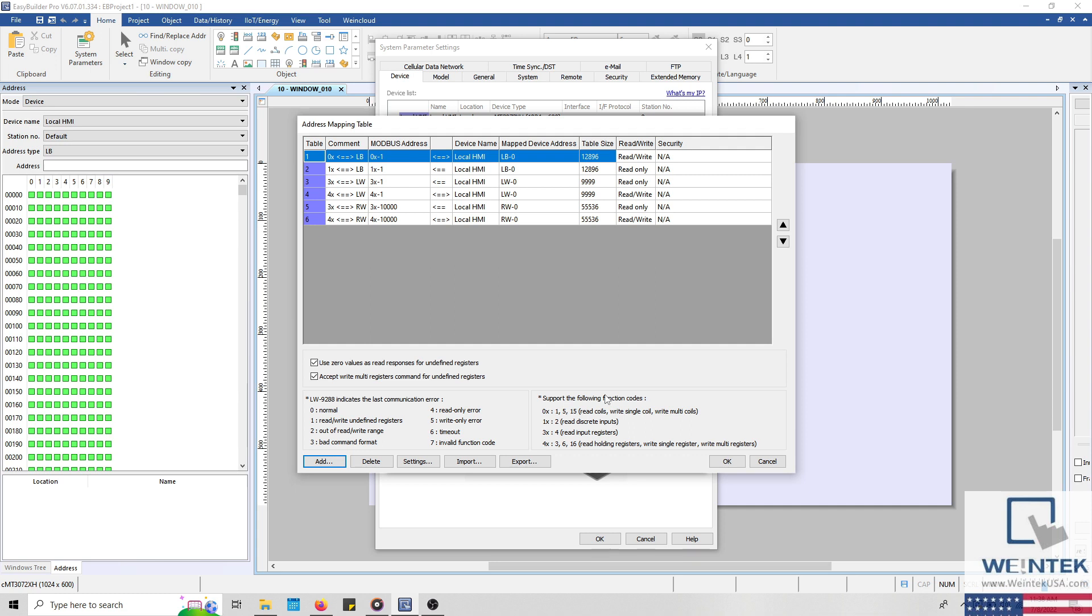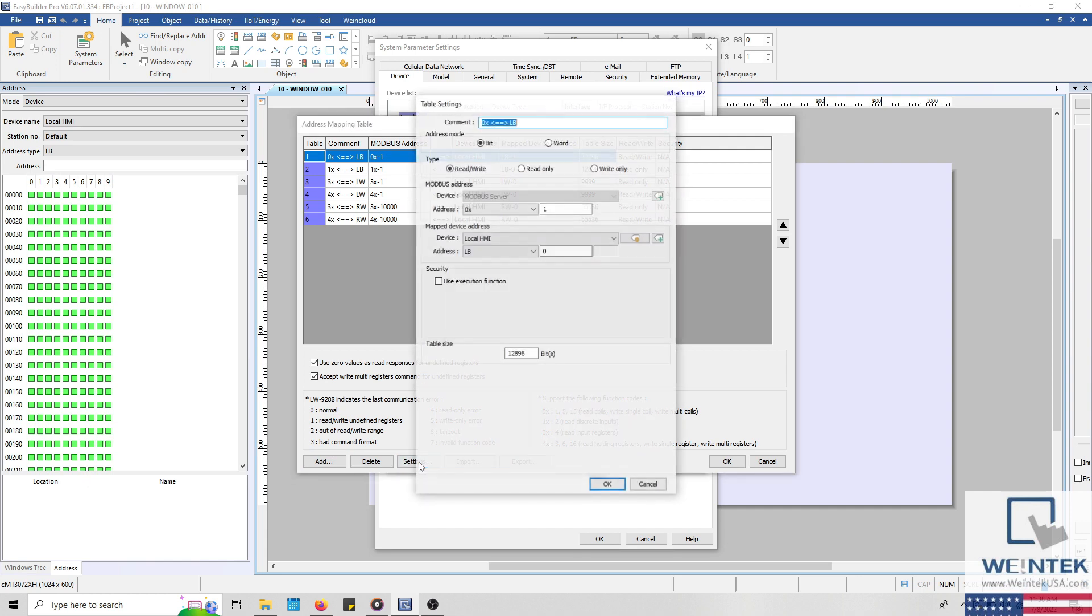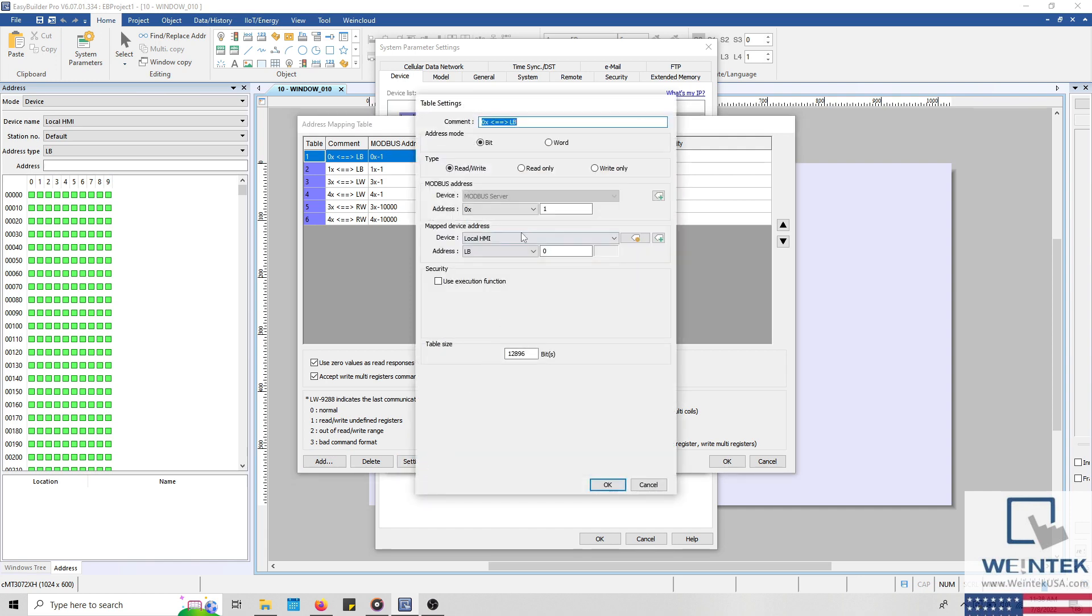Within this menu, we can add or remove a table using the add and delete button, while the settings button will allow us to reconfigure the Modbus mapping of a selected item. When configuring an item within this list, we can define the data type as either bit or word at the top. Within the type group box, we can specify read or write limitations. Near the center, we can define what Modbus address will be mapped to the specified device address. And at the bottom, we can define the table size and a byte or word swap.